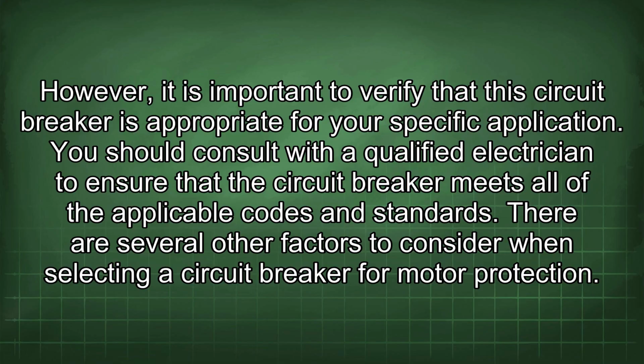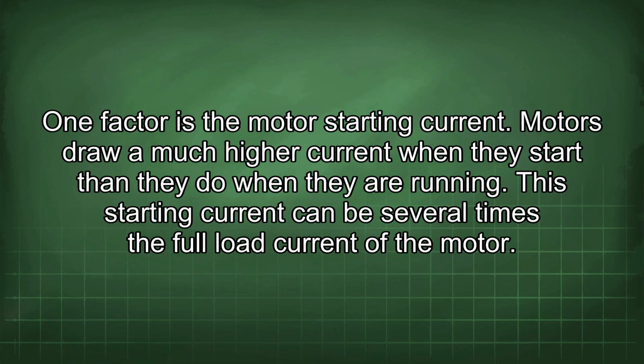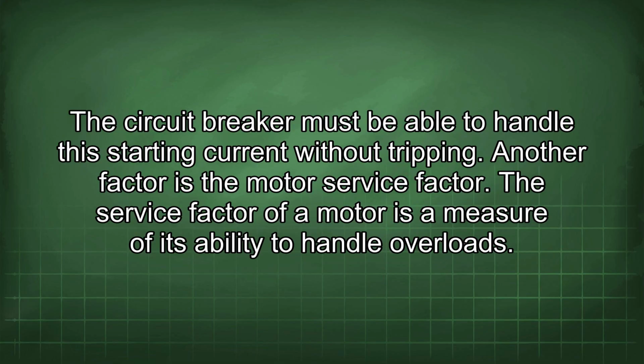You should consult with a qualified electrician to ensure that the circuit breaker meets all of the applicable codes and standards. There are several other factors to consider when selecting a circuit breaker for motor protection. One factor is the motor starting current. Motors draw much higher current when they start than they do when they are running. This starting current can be several times the full load current of the motor. The circuit breaker must be able to handle this starting current without tripping.